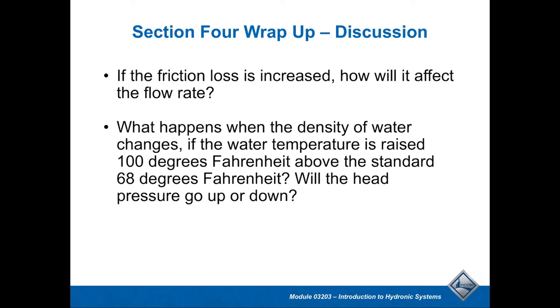To wrap up with some review questions: if the friction loss of the system increases — say a strainer is getting blocked up — that should actually cause our flow rate to go down. When the pressure drop in the system increases, that yields less water flow. Conversely, if you have more water flow, you will have a higher pressure drop.